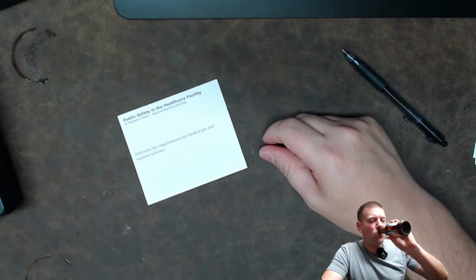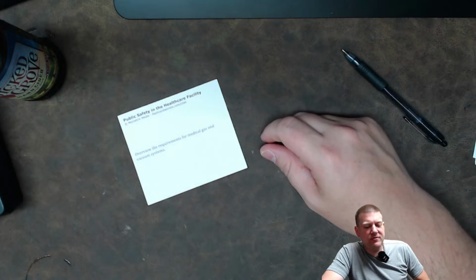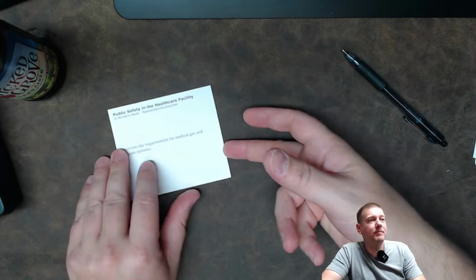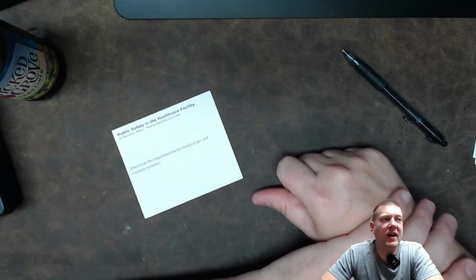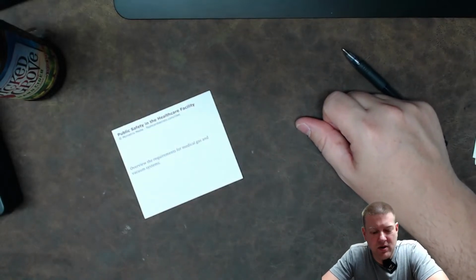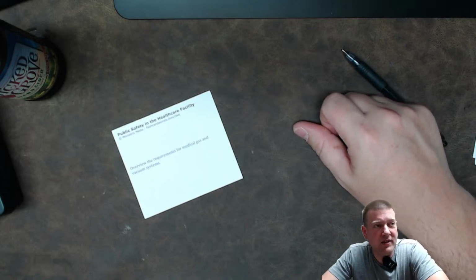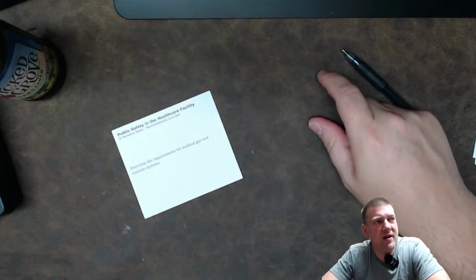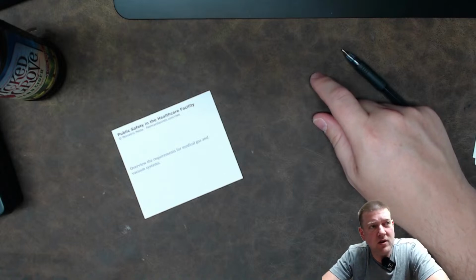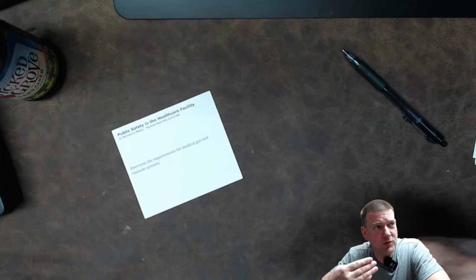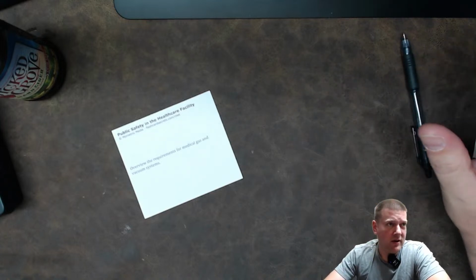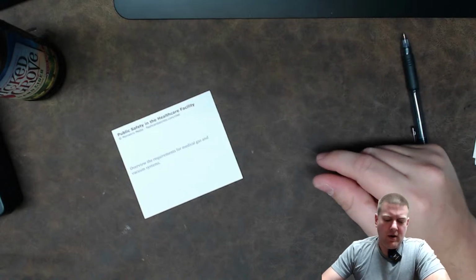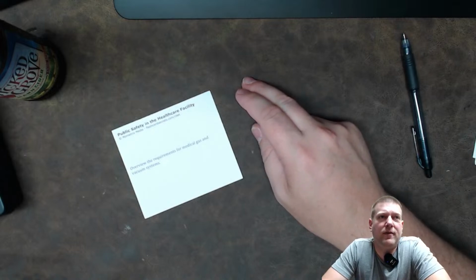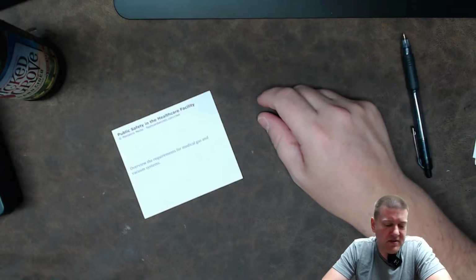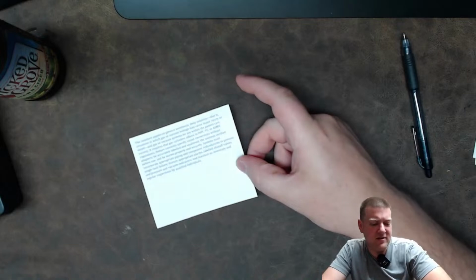Next, overview the requirements for medical gas and vacuum systems. Medical gas and vacuum systems have to have valves and gauges in zones, with clear labeling on every single one dictating what it is—carbon dioxide, nitrogen, oxygen, medical air, vacuum, WAG (waste anesthetic gas). You have all these lines, and they have to be labeled with sole connections, meaning without adapters you have one type of keyed connection. I know medical gases have to be tested for purity and flow at least annually. There's not too much else I can say about it—that's probably as good an answer as you're going to get.